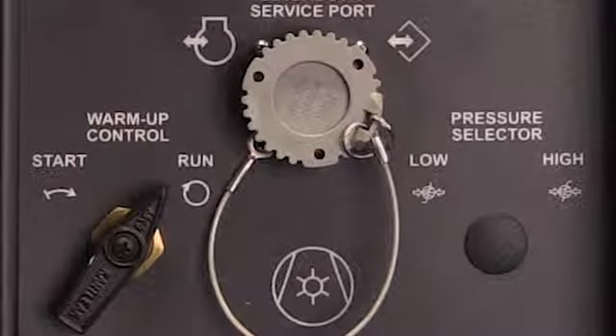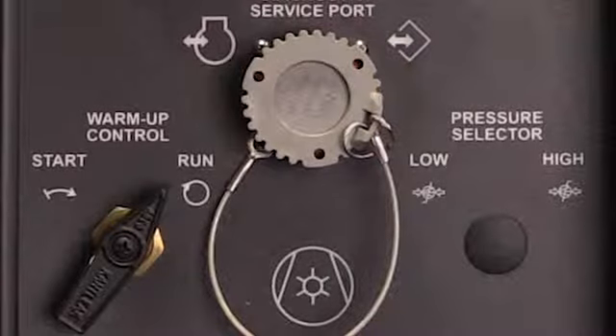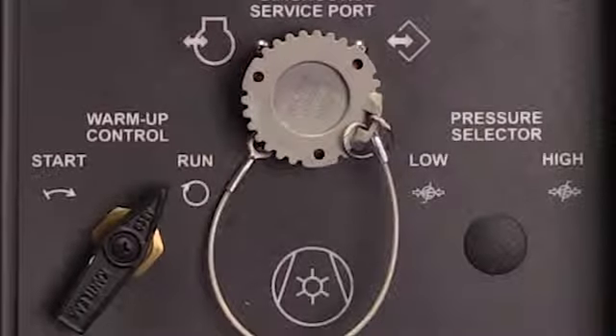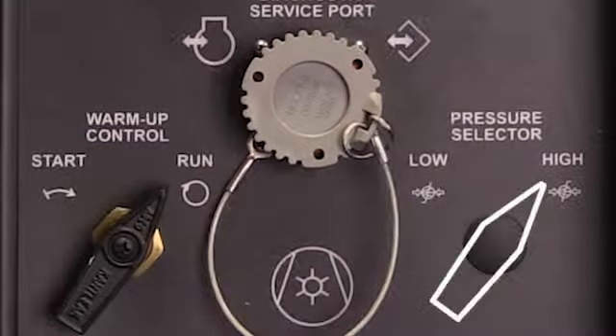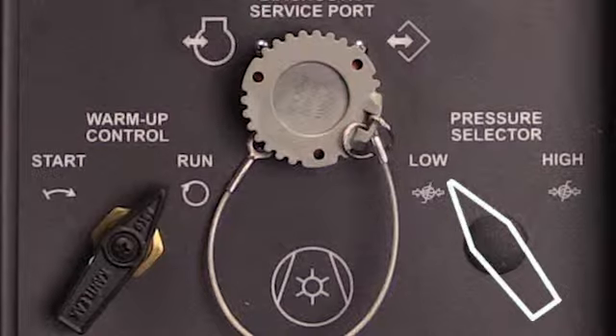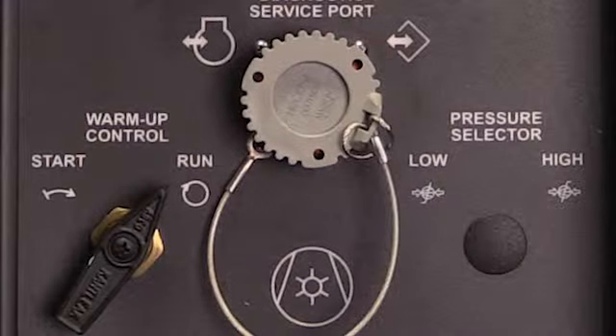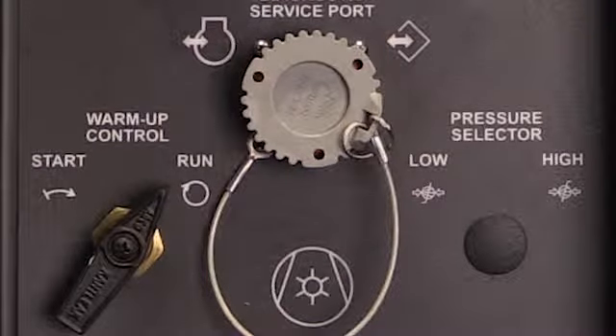What we'll demonstrate now is the proper shutdown procedure for a compressor. The first step applies to dual pressure machines only. Switch the high-low switch to low. Once you've done that, close the discharge valve. Never shut a compressor down with that valve open. The next step is optional, but recommended.